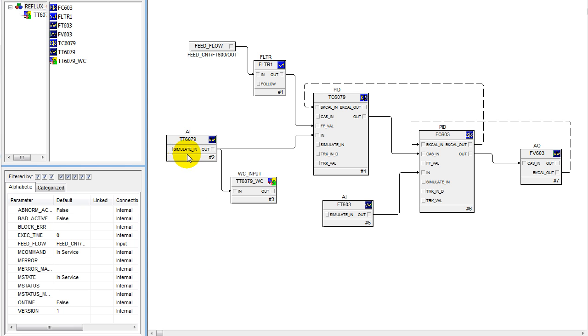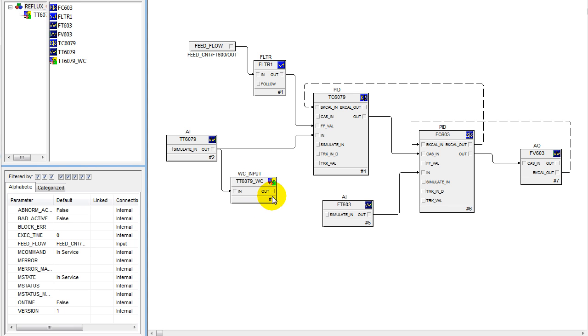For the top temperature, it's normally implemented as just a cascade control of temperature — the top temperature control loop cascaded to the reflux flow of the column. For implementation with model predictive control, we add a composite which is used to provide the temperature to the MPC.